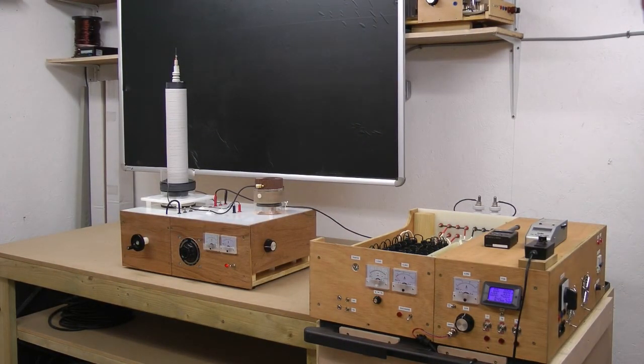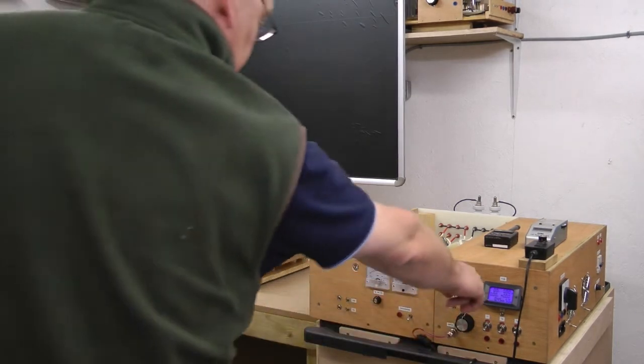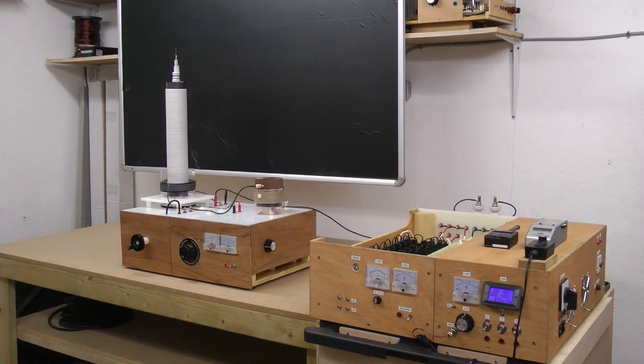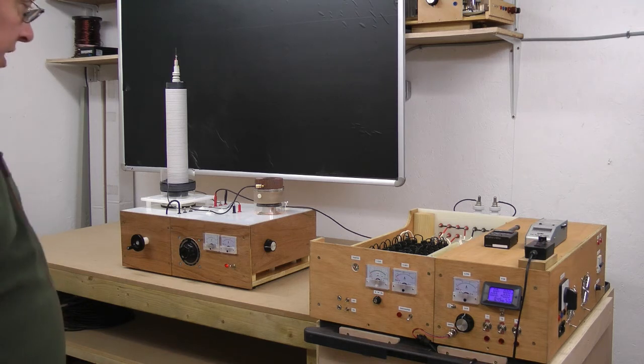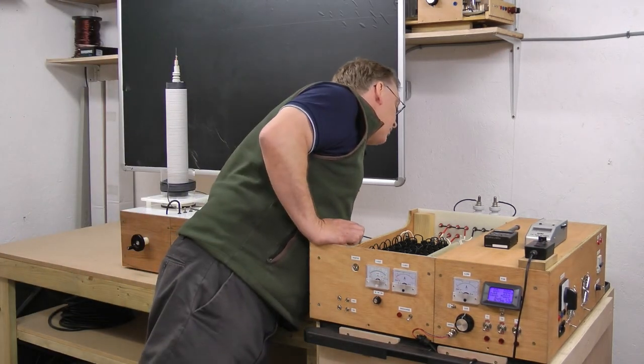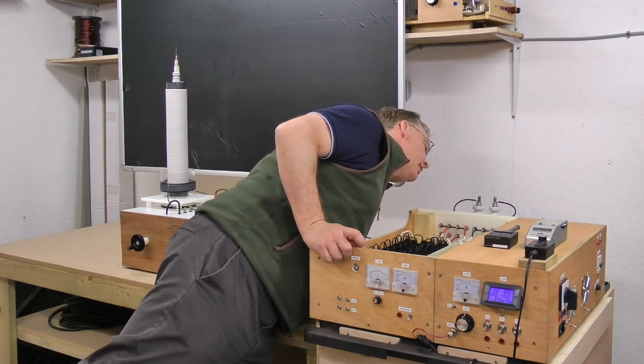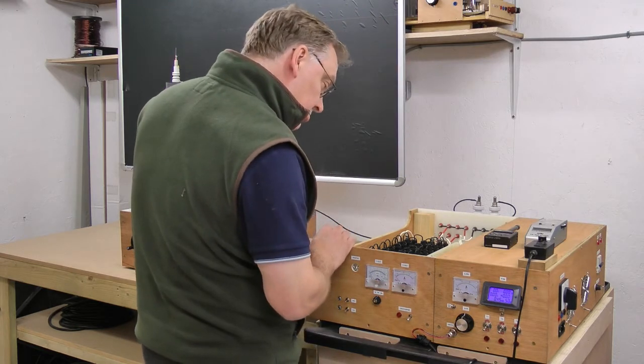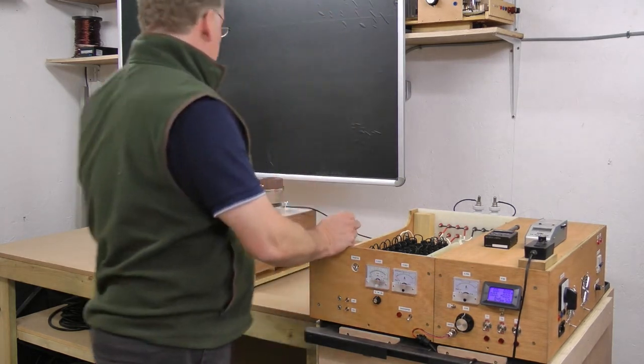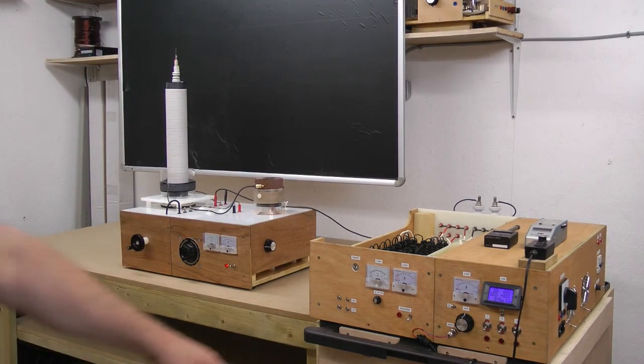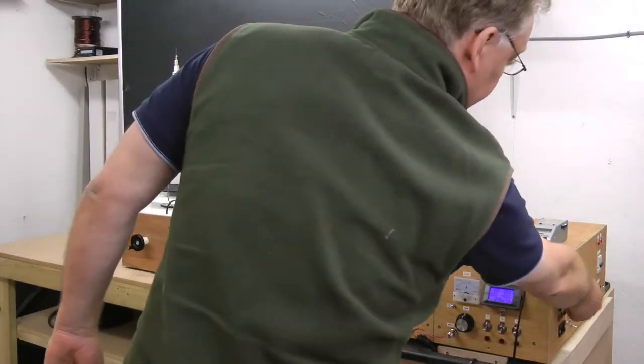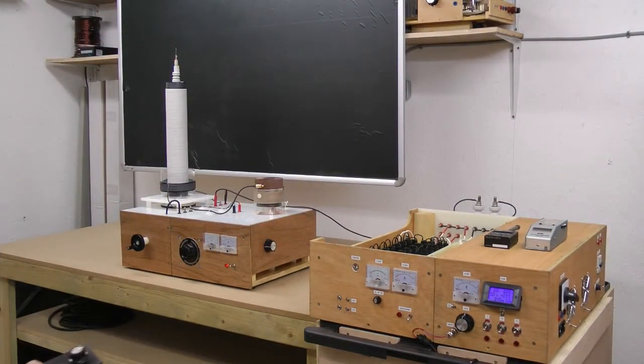In the meantime, I'll just turn this on, so the low tension's on, the high voltage is on, the power screen is also on, that's a complete power unit in one. It shows voltage, current and real power factor all together, particularly useful. Okay, I just have a final check, make sure everything's connected correctly. Using the rectifier. The rectifier is set here. Blocking capacitors connected and the high tension is connected as well. We've got two transformers selected. We set it to SCR, so SCR input, and we are basically using a remote control, so we don't have to get close to the system when we're running it.